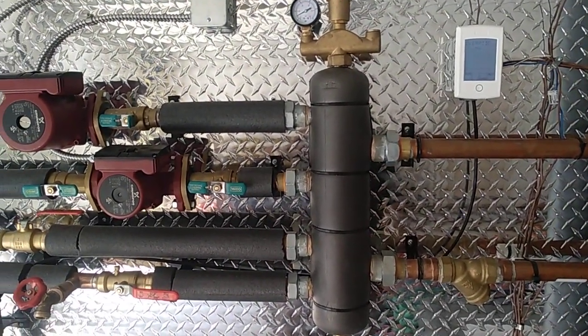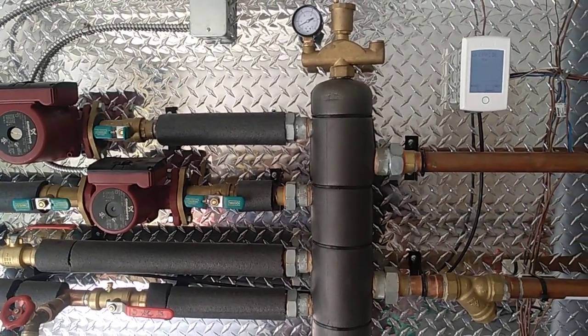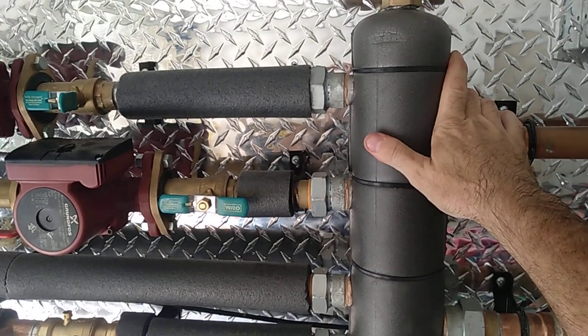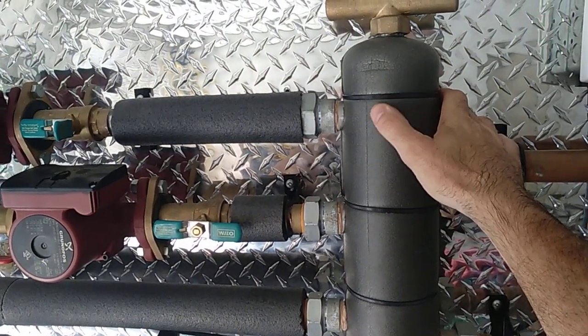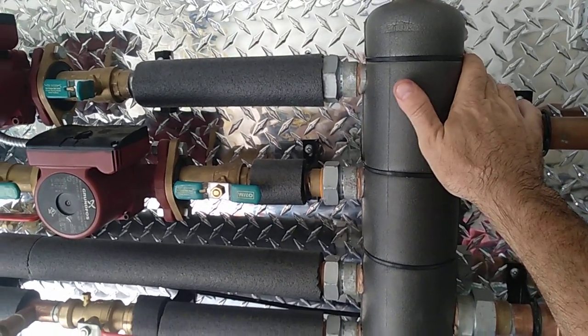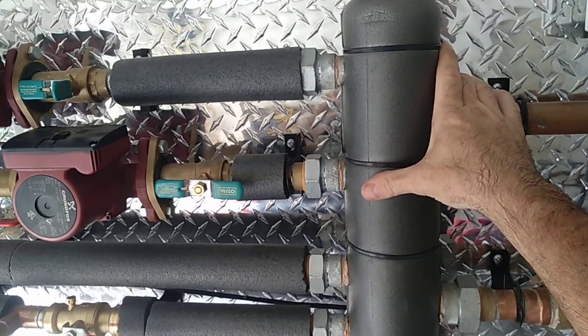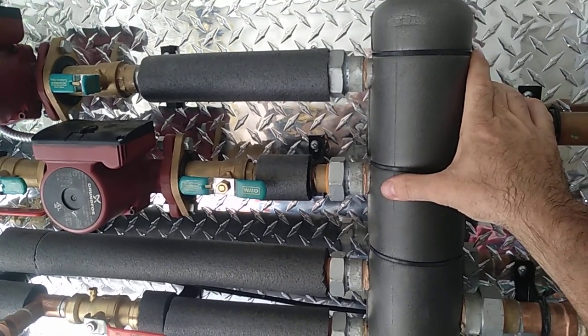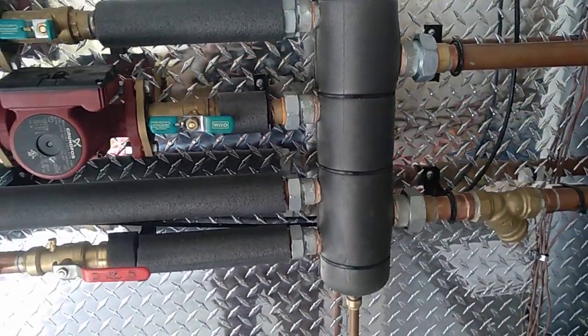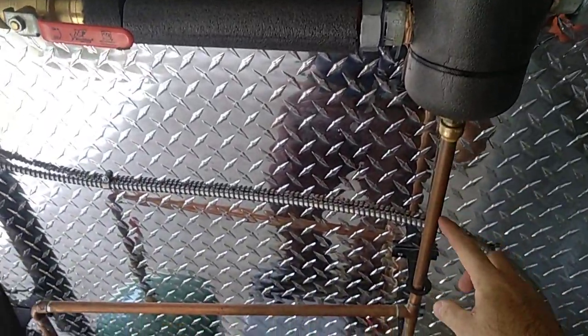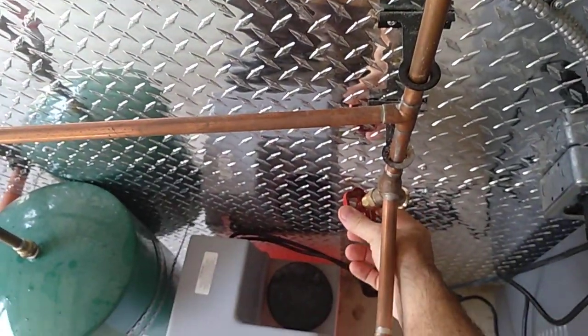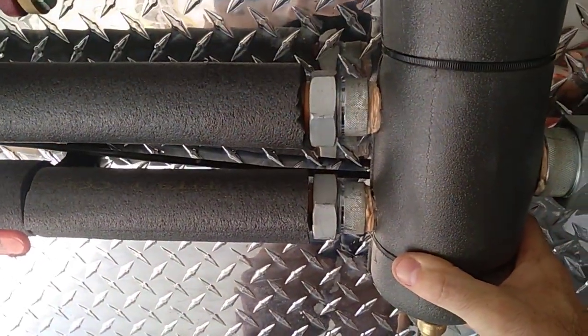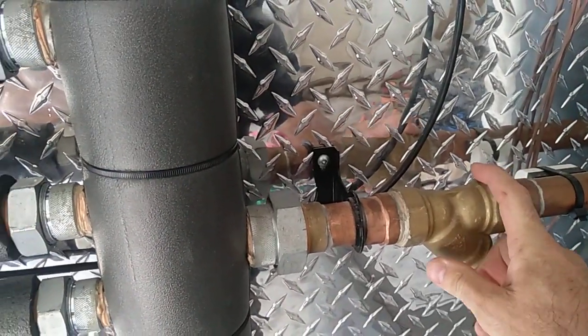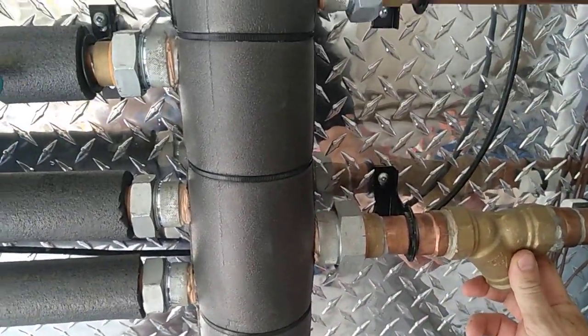Okay, about this hydraulic separator, why do we have this big tank here? There's several functions on this tank. Number one is that should there be any leftover garbage in the pipes in the system, rocks, pebbles, pieces of solder from soldering, it will not be circulated indefinitely and eventually potentially clogging up the boiler's heat exchanger, but it will settle to the bottom of this tank where we can just open this little valve and drain out the slush that accumulates on the bottom of this tank. Also there is a dirt strainer that is basically a filter, also protecting the pump and the boiler from sediment to clog up the heat exchanger.